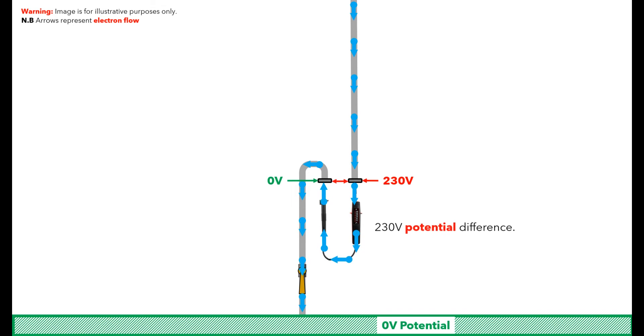With the voltage indicator connected to the difference in potential, the electrons will start to flow to that zero potential, and the potential difference will be displayed. This is why it is always a good idea to connect your test probes to the zero potential first, so that you are not waving the live end around.